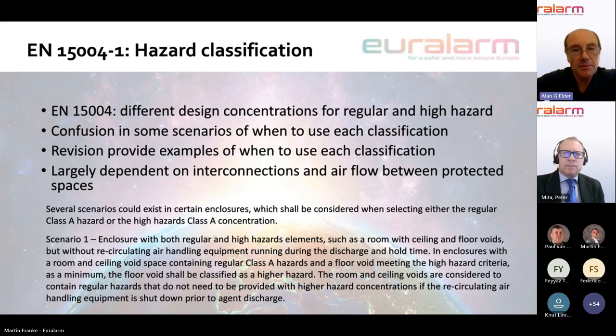This is one that is a little bit more complicated to explain. Within the ISO standard and subsequently in the EN standard, Class A hazards have been designated as either a regular Class A hazard or a high hazard Class A. This is a little different to what's contained within NFPA 2001, which talks of a regular Class A and then talks about a Class C hazard. And whilst the comparison between high hazard Class A and the US Class C are not identical, it is a similar definition of what would be included.